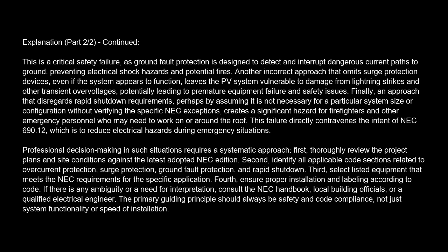Another incorrect approach that omits surge protection devices, even if the system appears to function, leaves the PV system vulnerable to damage from lightning strikes and other transient overvoltages, potentially leading to premature equipment failure and safety issues. Finally, an approach that disregards rapid shutdown requirements, perhaps by assuming it is not necessary for a particular system size or configuration without verifying the specific NEC exceptions, creates a significant hazard for firefighters and other emergency personnel who may need to work on or around the roof. This failure directly contravenes the intent of NEC 690.12, which is to reduce electrical hazards during emergency situations.